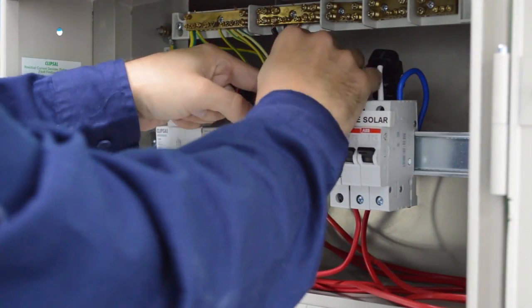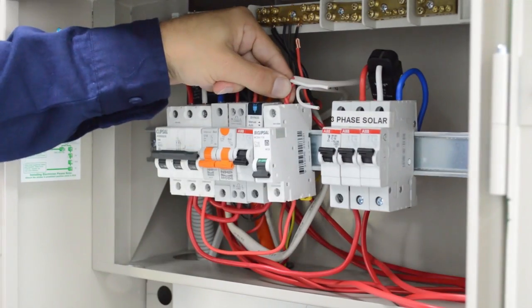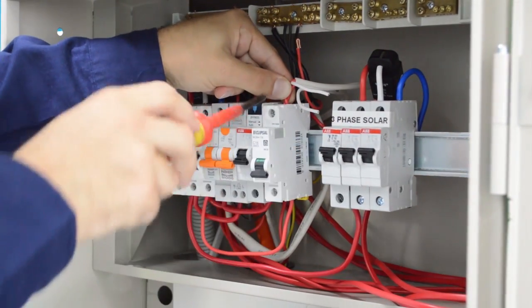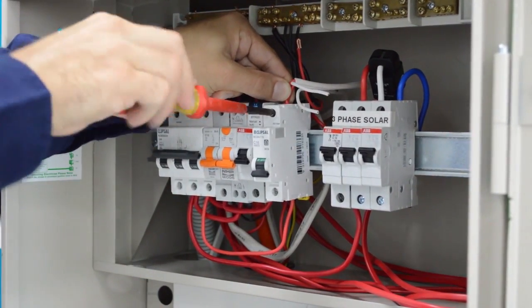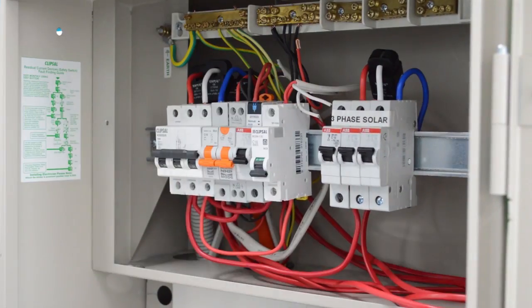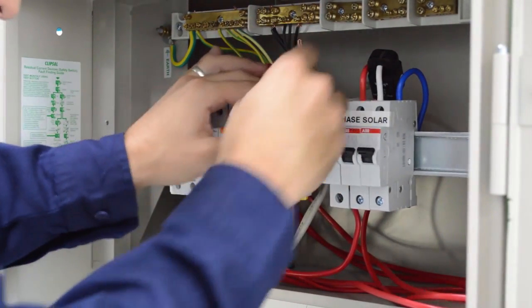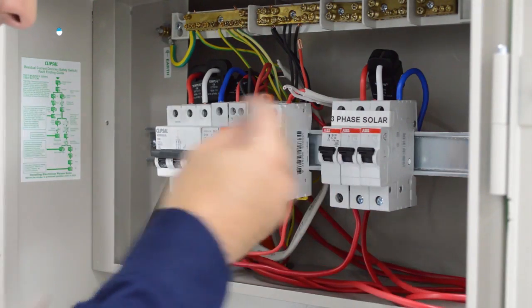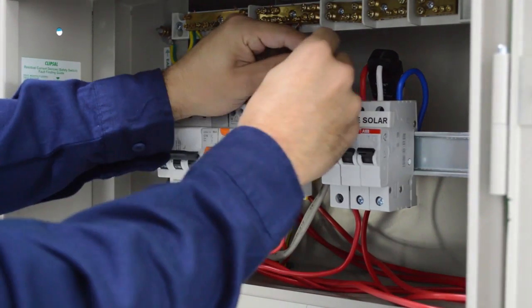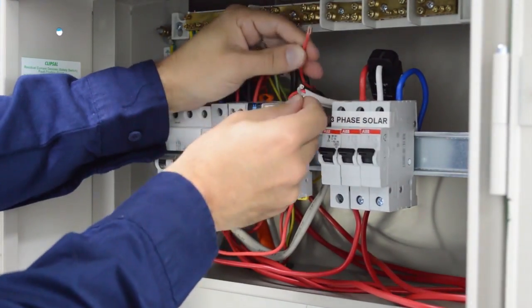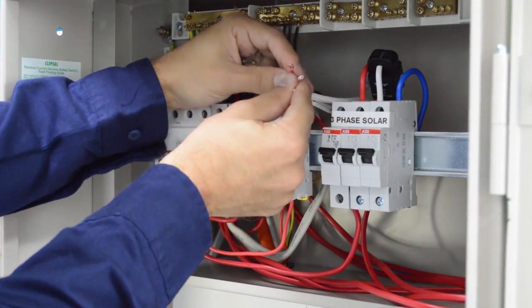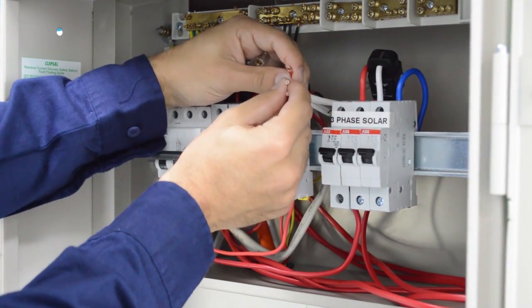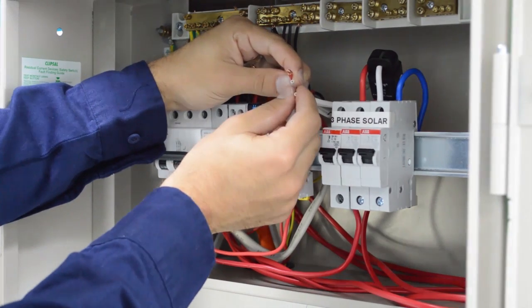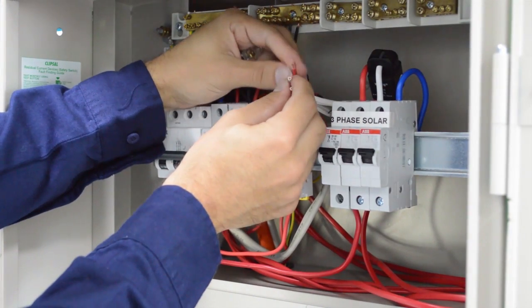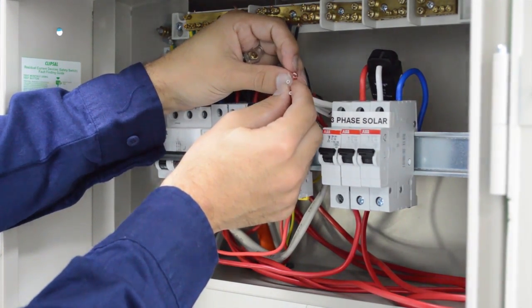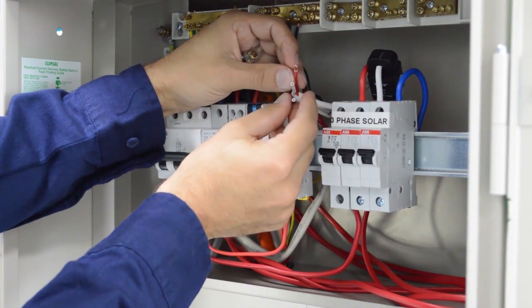into the circuit breaker. I must stress that these must be powered from the circuit breaker of the circuit being switched. Now, using a screw connector, I'm going to connect the load active with the 2 whites of the twin actives which we have run, 1 for the relay and 1 for the bypass switch. This is connecting the bypass switch and the relay in parallel.